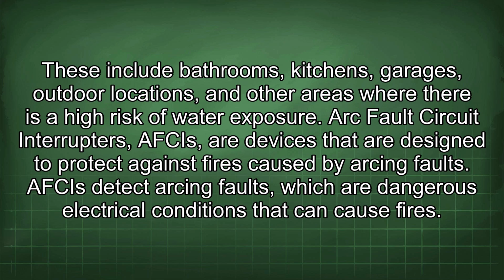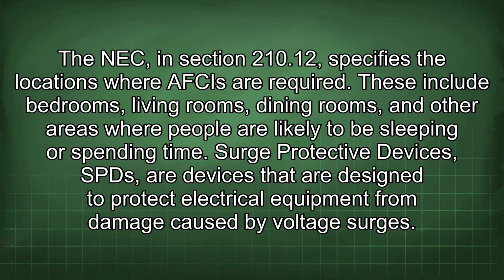Arc fault circuit interrupters, AFCIs, are devices that are designed to protect against fires caused by arcing faults. AFCIs detect arcing faults, which are dangerous electrical conditions that can cause fires. The NEC in section 210.12 specifies the locations where AFCIs are required. These include bedrooms, living rooms, dining rooms, and other areas where people are likely to be sleeping or spending time.